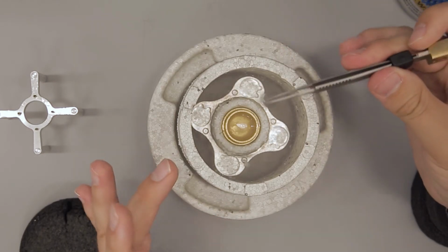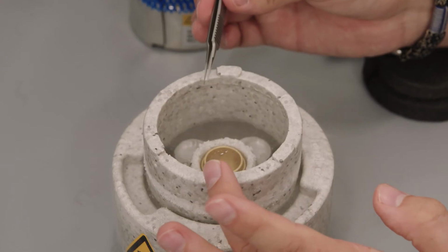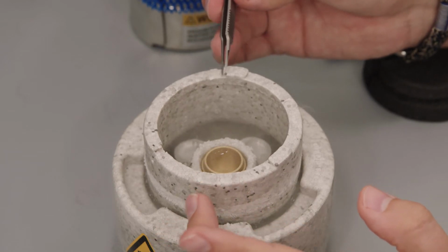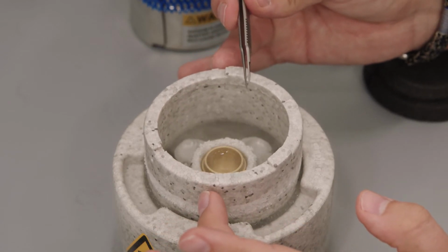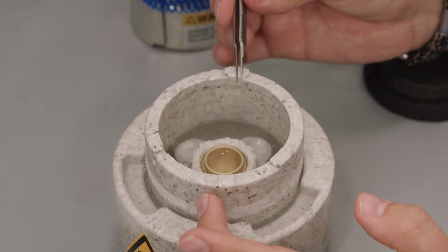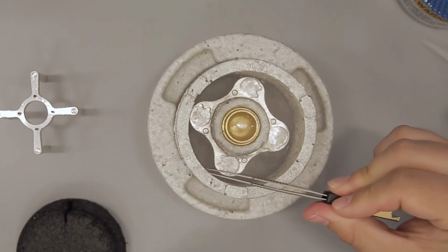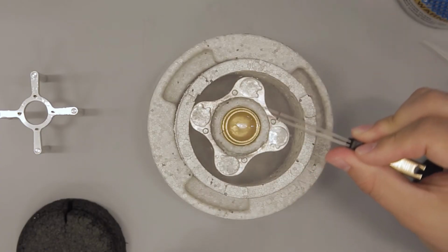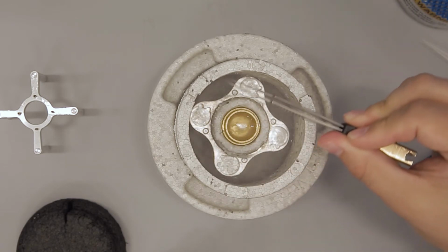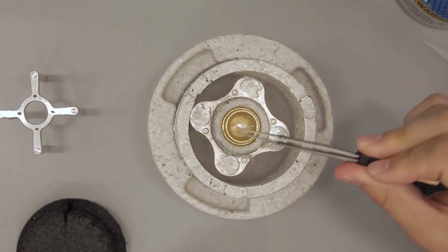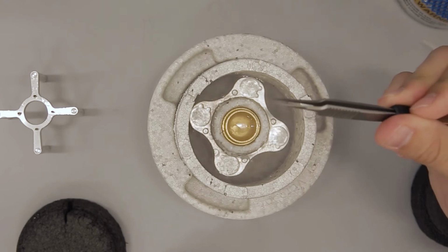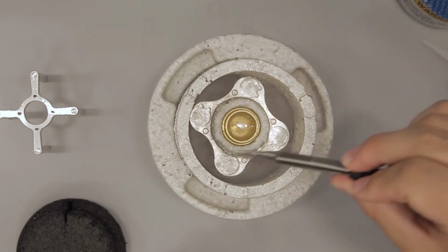The next form of contamination comes from the anti-contaminator ring. There are some labs that actually don't use the ring at all. I would advise to always use it, because you can see that at the surface of this ring you'll see some vapor layer being formed. And this is the interface between the warm air and the nitrogen vapor.